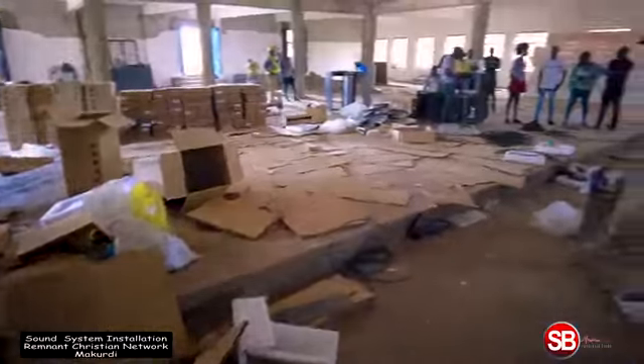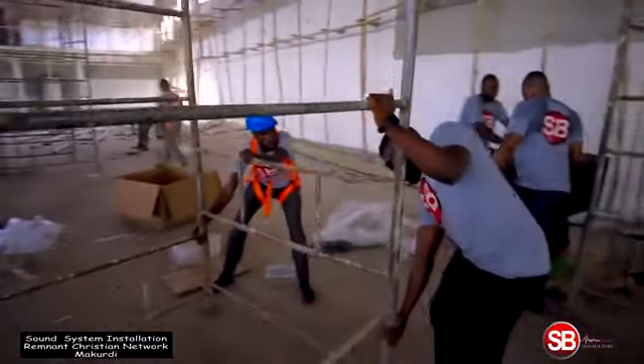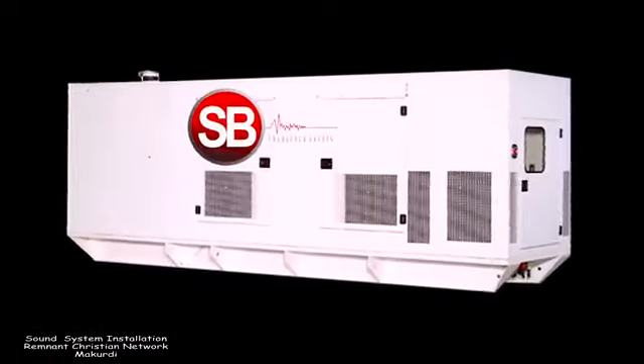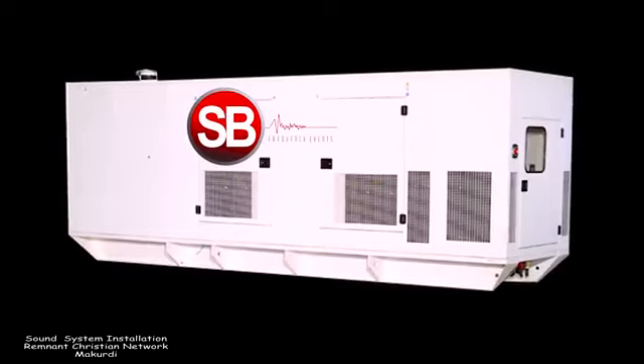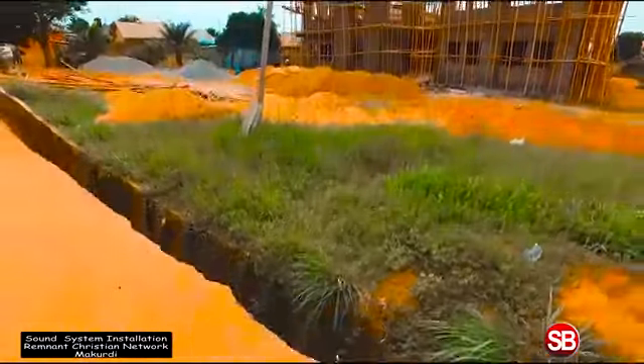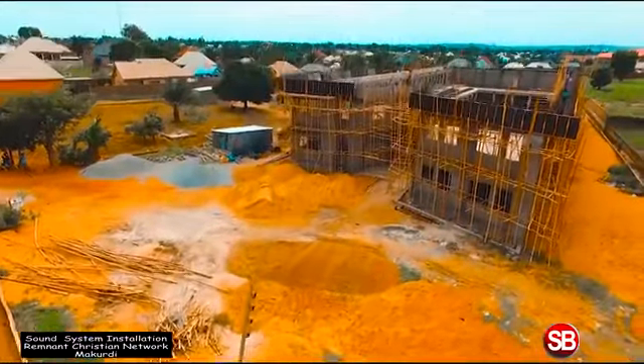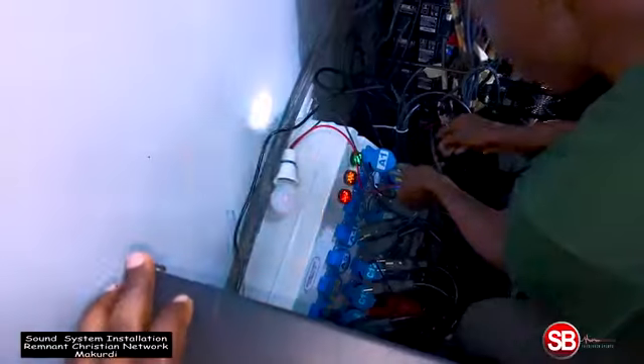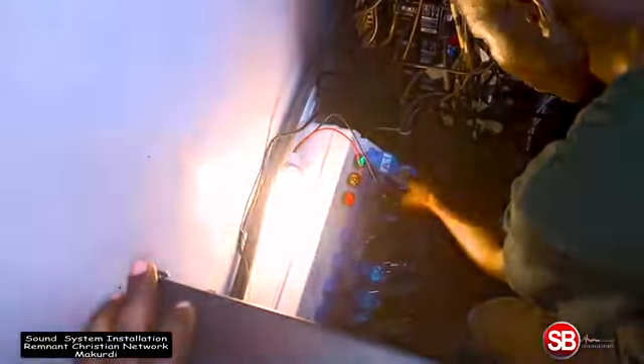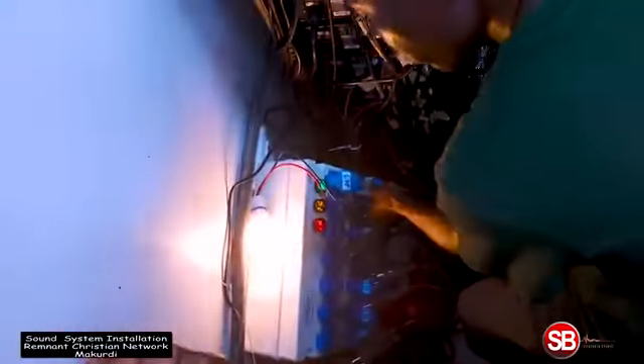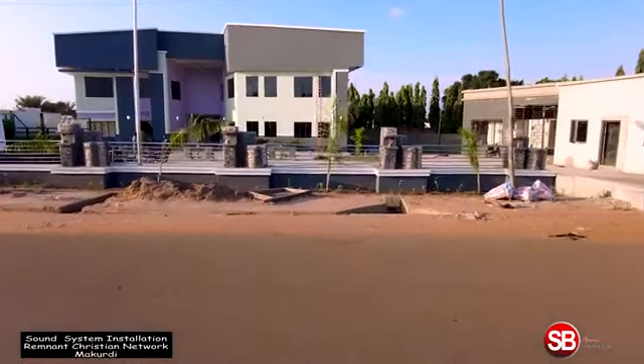On every installation, we have challenges. Aside the delays caused by other vendors, we had a major electrical challenge. The generator provided for the entire building was too powerful for the sound system, 500 kVA. Also, the earthing wasn't right as the building environment was a waterlogged area. Generator sets are designed to operate with substantial load. Standby rated diesel gens are designed to operate between 50 and 80% load, while continuous rated diesel generator sets are optimized between 70 and 100% load.